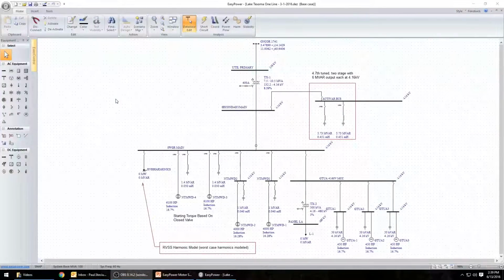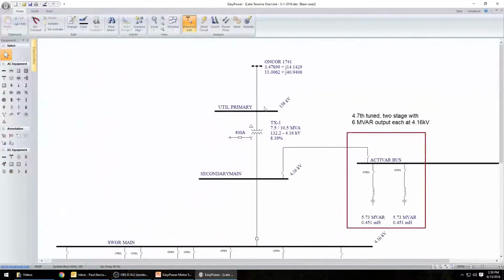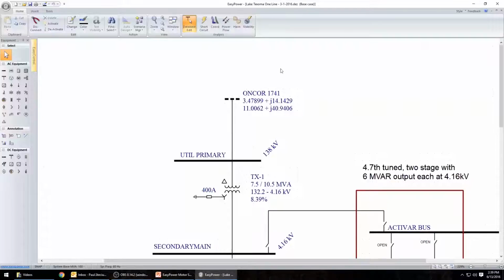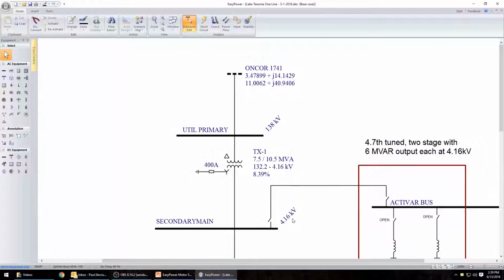Here's a case study for an application of the actiVAR. Okay, so I want to review the one-line diagram real quick. We have an incoming swing bus here with a primary voltage of 138 kV, a secondary voltage of 4.16 kV. It has a rating of 7.5 MVA with an 8.4% impedance.